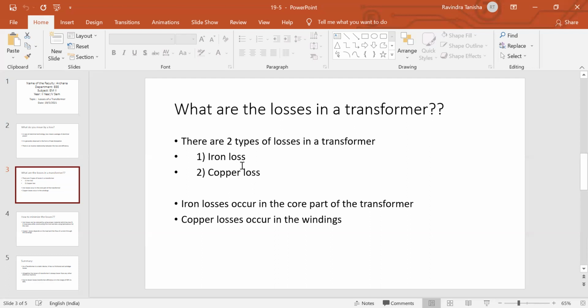Copper loss generally occurs in the winding part, because windings are made of copper material. So copper loss always occurs in the winding part, whereas iron loss, the constant loss or core loss, occurs in the core part of the transformer. As the core is made of iron material, these losses are called iron loss, the constant loss. This iron loss never depends on the load or the load current, whereas copper loss always depends on the load and load current. This load current is always varying. That's why copper loss is a variable loss, whereas iron loss does not depend on the amount of load current. That's the reason iron loss is a constant loss.